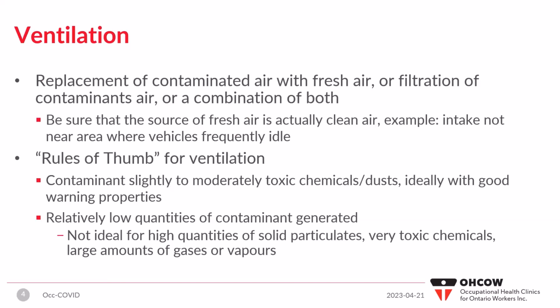A couple of rules of thumb for ventilation. This is excellent for contaminants that are slightly to moderately toxic, ideally with a good warning property, but it doesn't have to. And relatively low quantities of contaminants are generated. So you are not using general ventilation where there are high quantities of solid particulates. So it's so dusty you can't see anything. General dilution ventilation is not going to be enough for that. So we're talking offices, we're talking healthcare settings, right? Although there is sometimes local exhaust in healthcare. We're talking factories that don't have lots of chemicals in them.